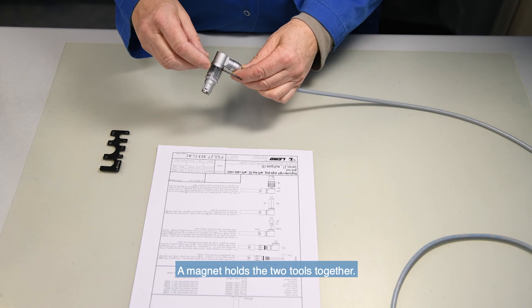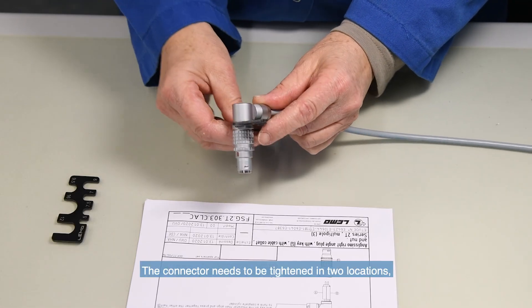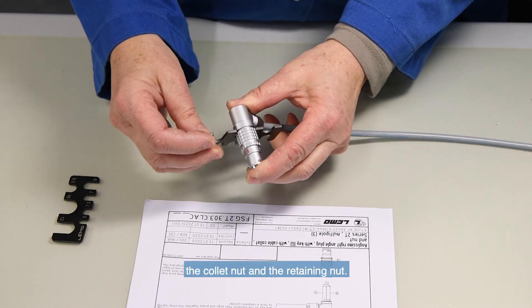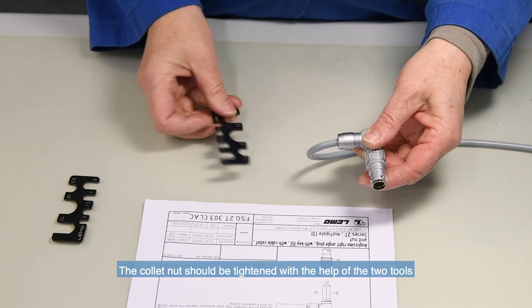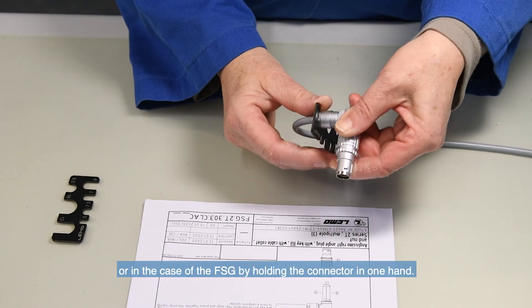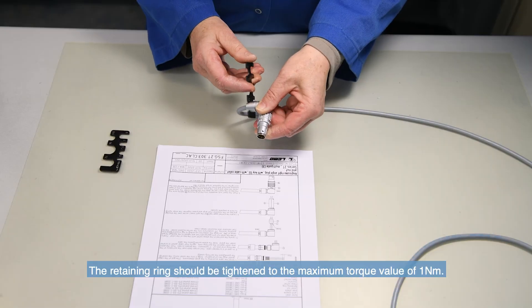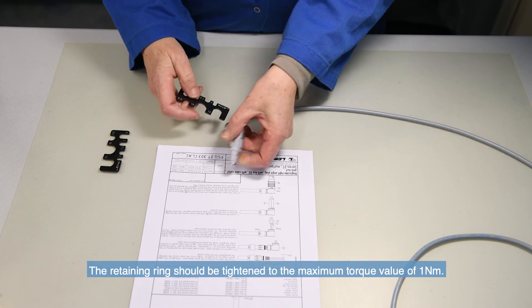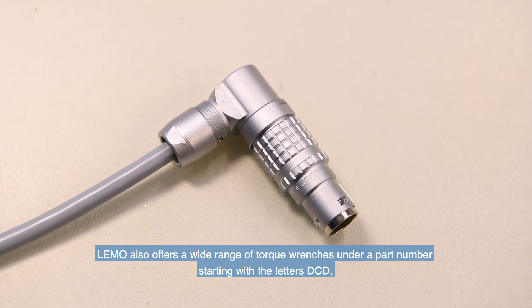A magnet holds the two tools together. The connector needs to be tightened in two locations: the collet nut and the retaining nut. The collet nut should be tightened with the help of the two tools, or in the case of the FSG, by holding the connector in one hand. The retaining ring should be tightened to the maximum torque value of 1 Nm. LEMO also offers a wide range of torque wrenches under part numbers starting with the letters DCD. The tool is visible at the end of the Unipole multipole catalogue.